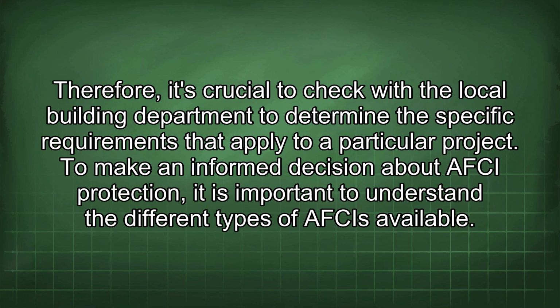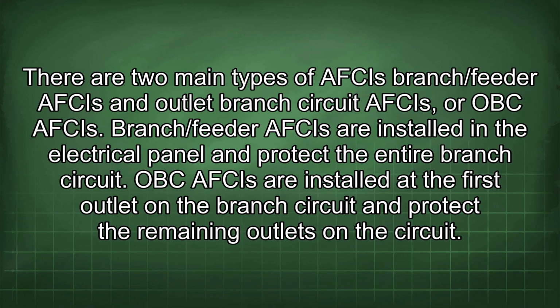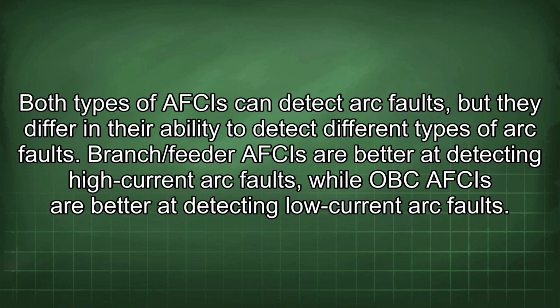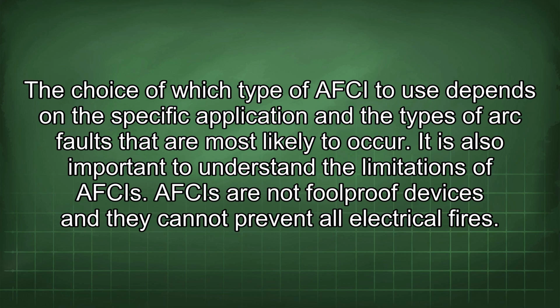To make an informed decision about AFCI protection, it is important to understand the different types of AFCIs available. There are two main types of AFCIs: branch/feeder AFCIs and outlet branch circuit AFCIs, or OBC AFCIs. Branch/feeder AFCIs are installed in the electrical panel and protect the entire branch circuit. OBC AFCIs are installed at the first outlet on the branch circuit and protect the remaining outlets on the circuit. Both types of AFCIs can detect arc faults, but they differ in their ability to detect different types of arc faults. Branch/feeder AFCIs are better at detecting high current arc faults, while OBC AFCIs are better at detecting low current arc faults. The choice of which type of AFCI to use depends on the specific application and the types of arc faults that are most likely to occur.